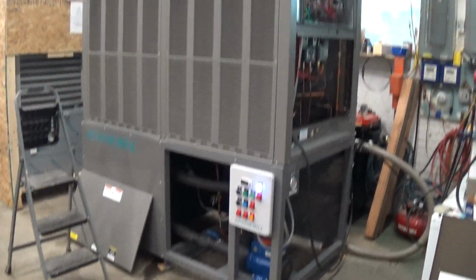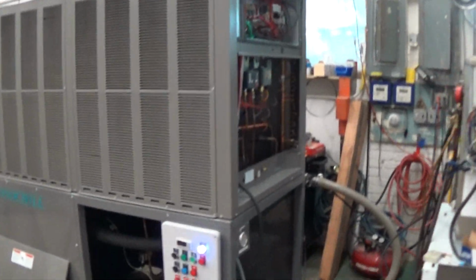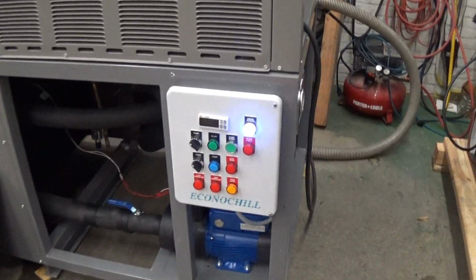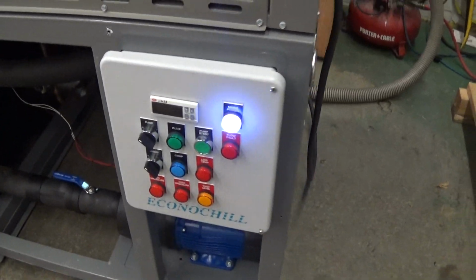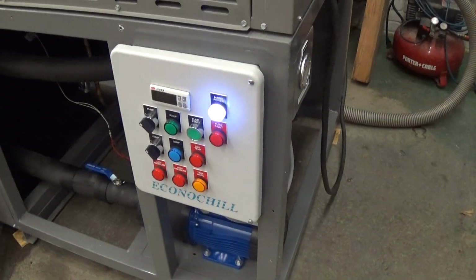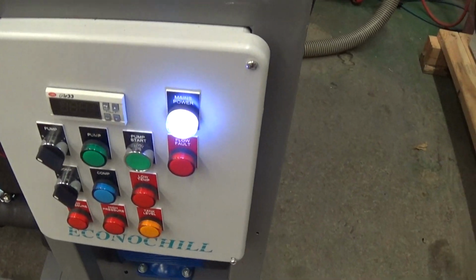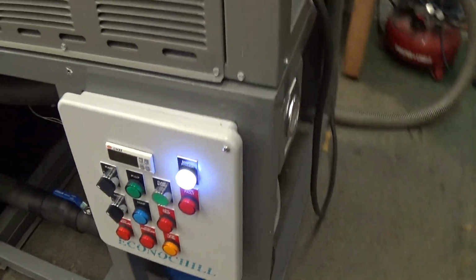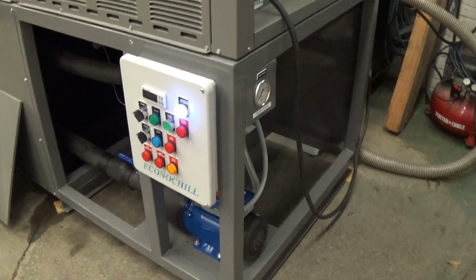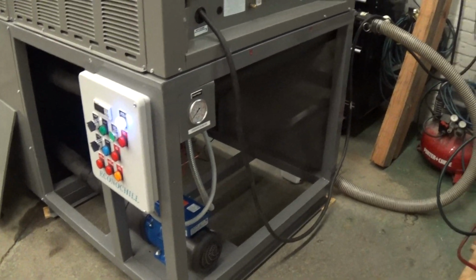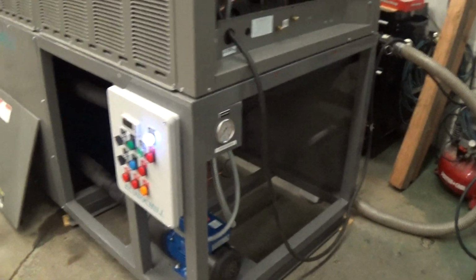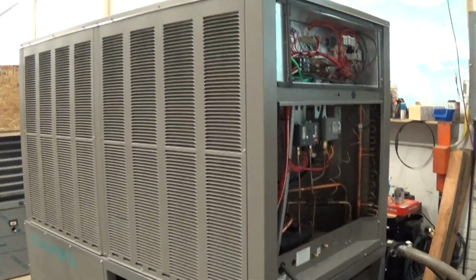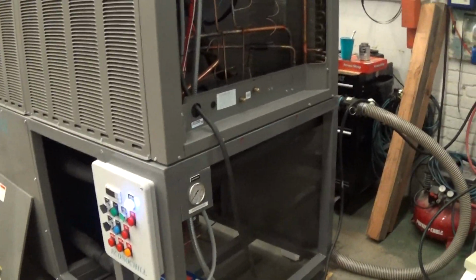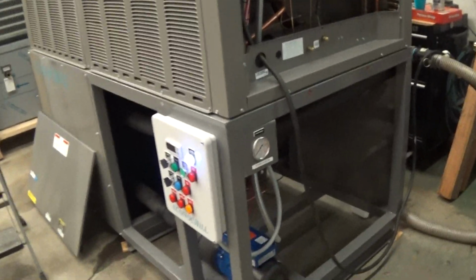This is our video number 3 for the 10-ton Econochill chiller. One thing, you see I have the main power light on here. The main power light is on as long as you have live power connected to the machine. And we encourage you after your installation to always leave the main power on unless it's going to be shut down for weeks and weeks at a time.